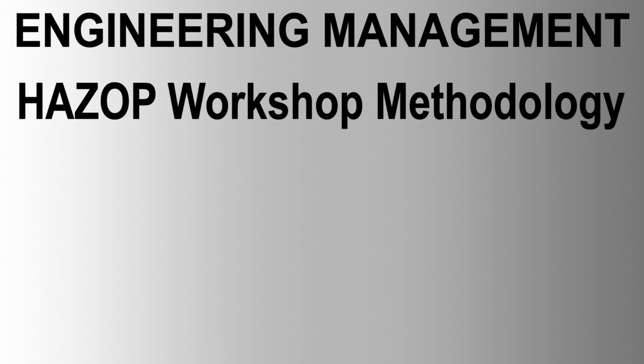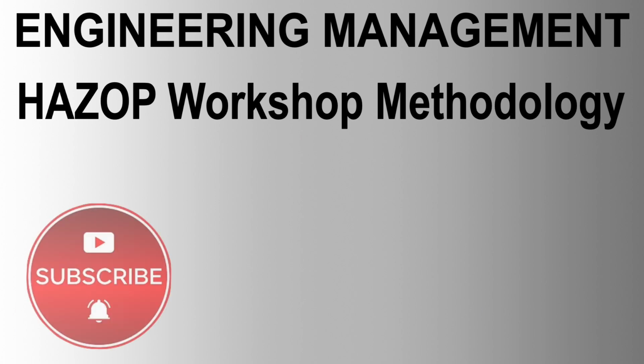Collect information. Gather all relevant documentation such as process and instrumentation diagrams (P&IDs), process flow diagrams, operating procedures, and safety data sheets. 2. Kickoff meeting, introduction. Introduce the HAZOP methodology and objectives to the team. Terms of reference. Review the terms of reference, scope, and schedule for the study. Roles and responsibilities. Clarify the roles and responsibilities of each team member.